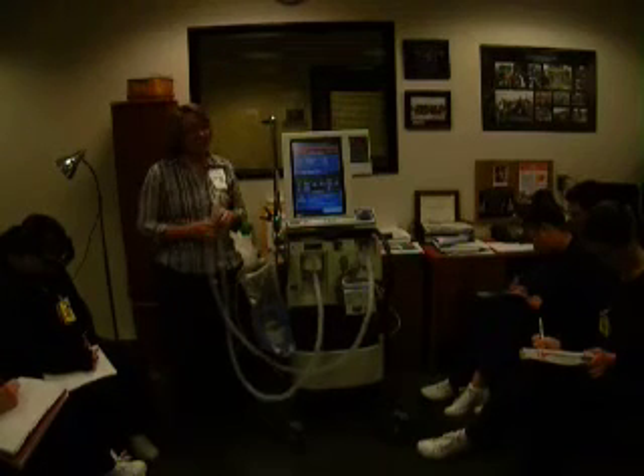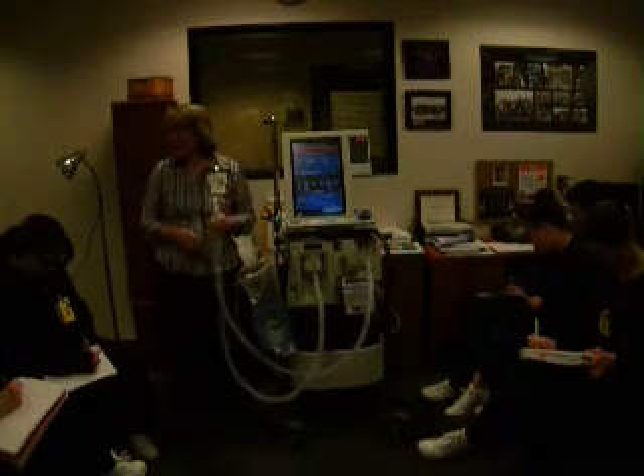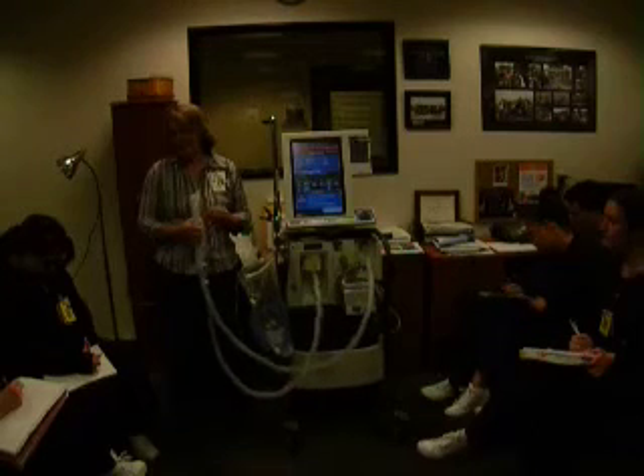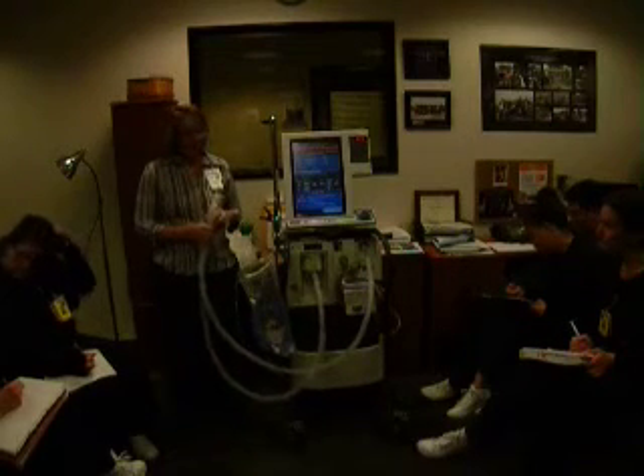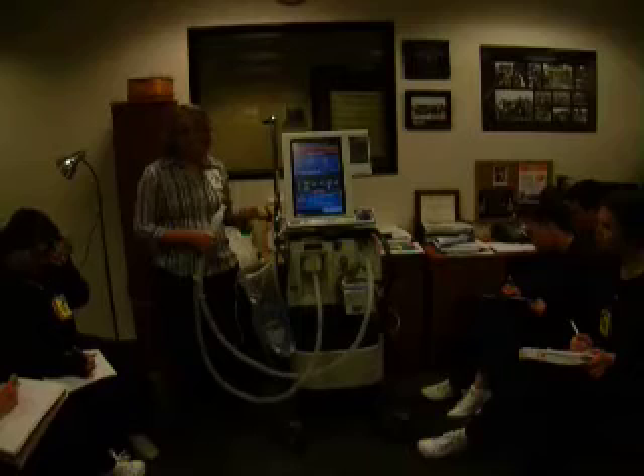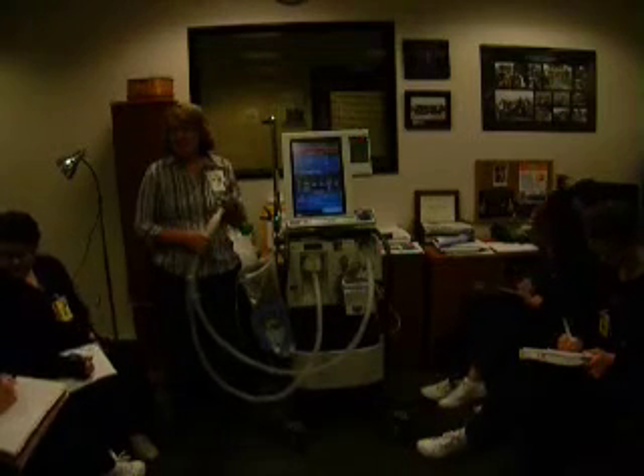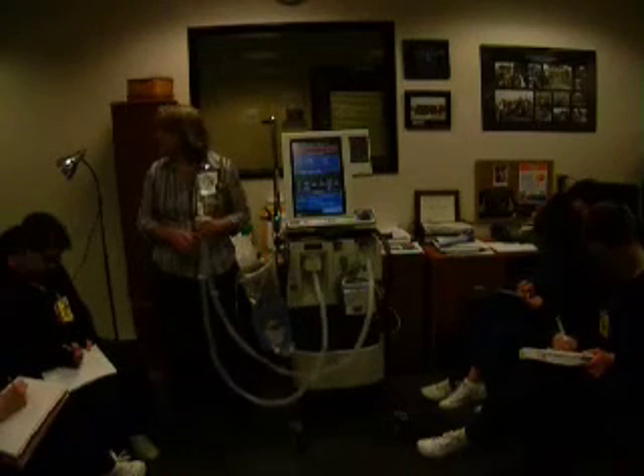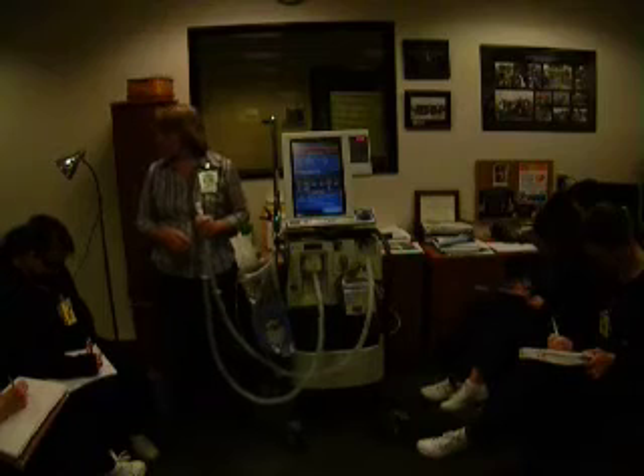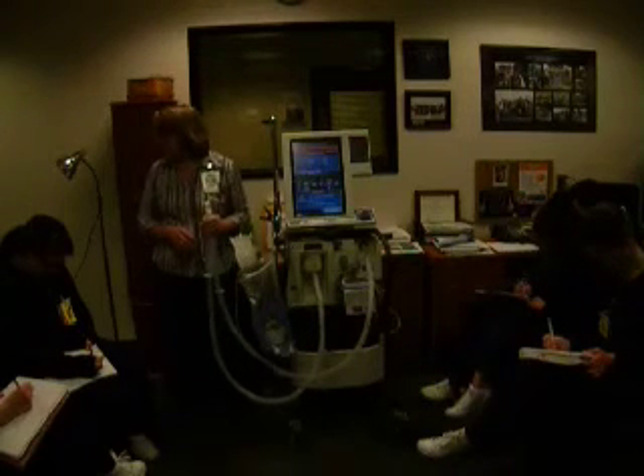And it's actually a 3-minute test. It seems like it takes 15, but it's really only 3. And what we're doing is checking all the internal components, checking the alarms, checking for leaks in the system. Yes? What was the SST? Short self-test. Short like tall and short, yeah.